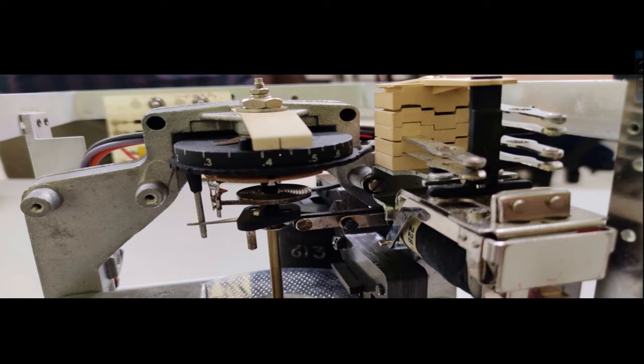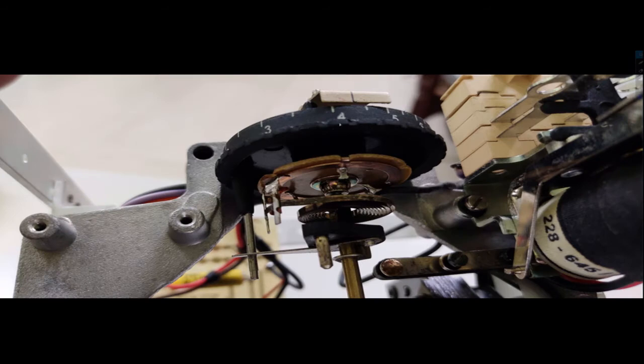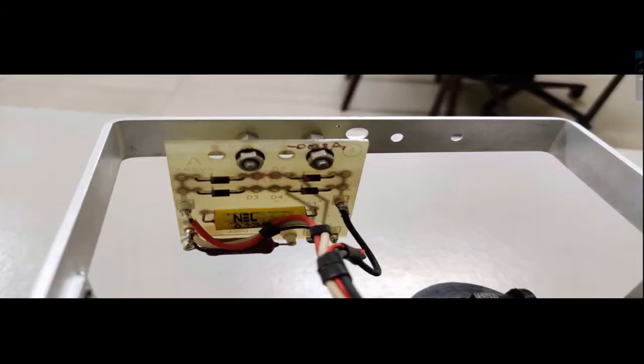So that is controlled by this particular disk. That's why the name of this thing is a time setting multiplier. As you see, this portion needs to be closed by that particular arrangement, and this is the backstop. Due to that, this disk is not able to move beyond that point. This is called the initial position or the backstop, so if you adjust the position of this backstop, then sometimes the relay needs a long time to operate or to generate the trip signal, and sometimes the relay needs very short time to operate the trip signal. So this is controlled by this dial, which is called the time setting multiplier.